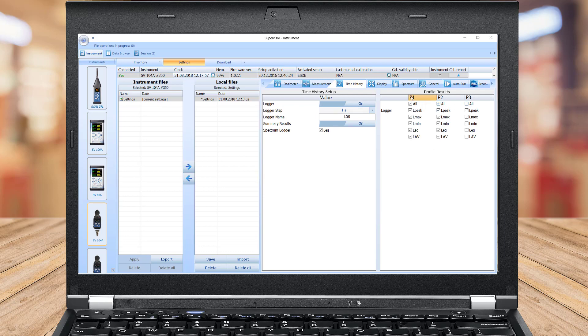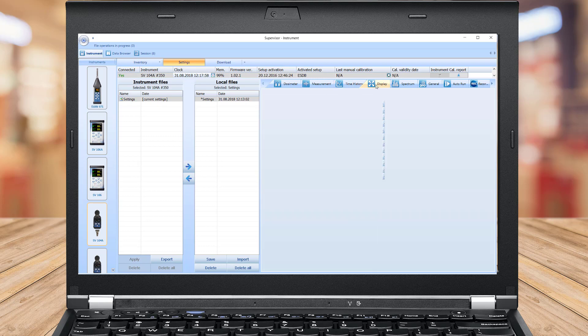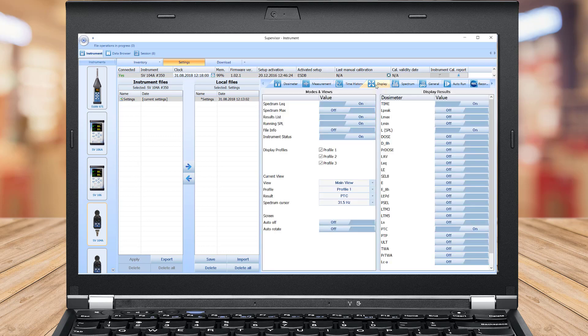There are quite a few view modes accessible on the display when the dosimeter is performing a measurement. In the left panel named Modes Views, you can select which view mode will be present when you press the Enter key on the dosimeter keypad. In the right panel named Display Results, you will find a list of over a dozen measurement parameters that can be configured to be presented on the SV-104A display when you press scroll.